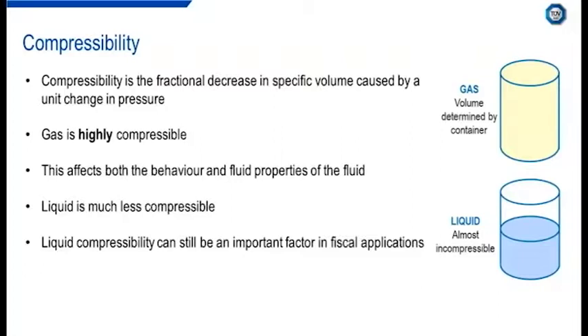Liquid compressibility, however, can still be important to account for in fiscal applications, for example, where low measurement uncertainty is required, particularly at elevated pressure, where it is no longer fair to assume that oil, for example, is incompressible.